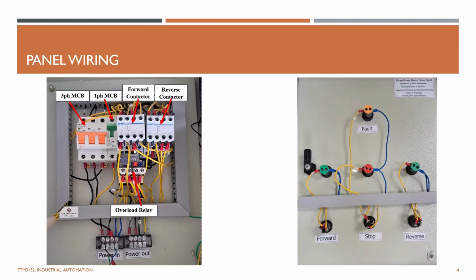Here you can see the two contactors. This is a forward contactor. On top of that, there's an auxiliary contactor for additional normally open and normally closed contacts, which is used for light indicators. Because when you purchase a contactor, only a few normally open and normally closed contacts come with it. But when you want to do additional wiring for indicators, you need to purchase these white color auxiliary contact points. Here you can see the reverse contactor and its auxiliary contact point.